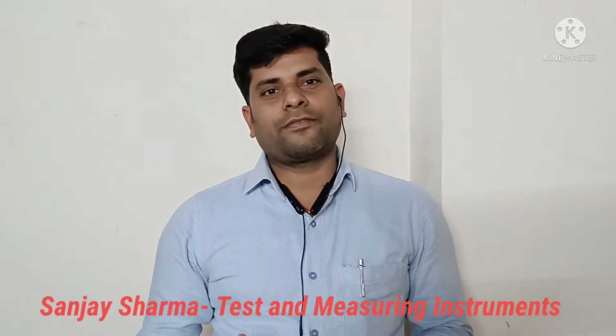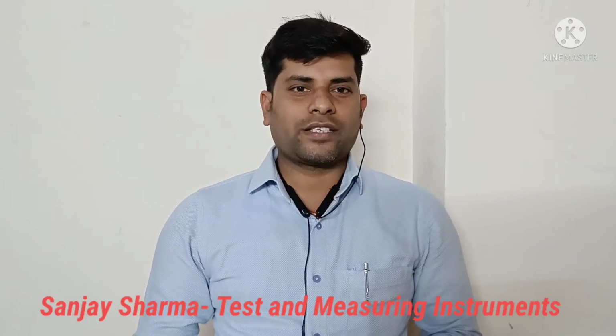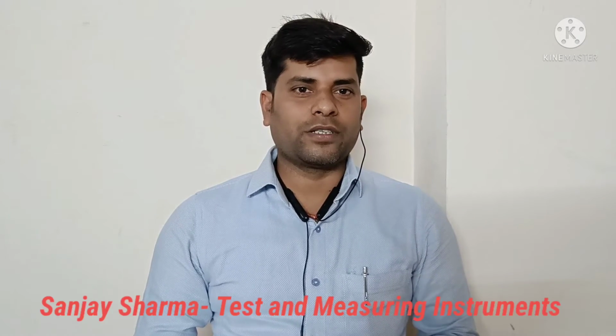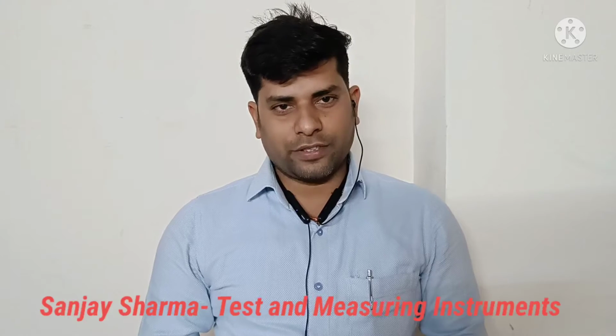It is plus minus 1.5%. It can also perform rise time and fall time control, so you can set your required rise time voltage. Suppose you have set 1 kV voltage for testing purposes. If you want to increase it in a ramp, that is the function utilized in the rise time function.